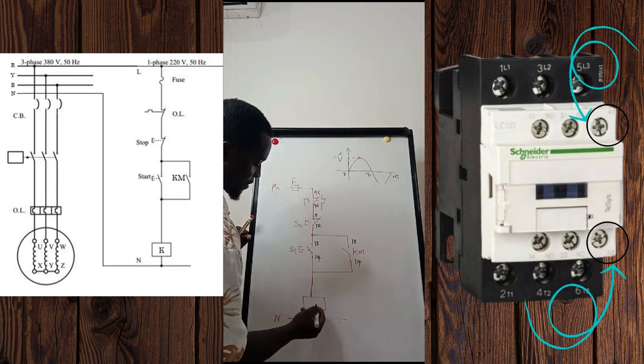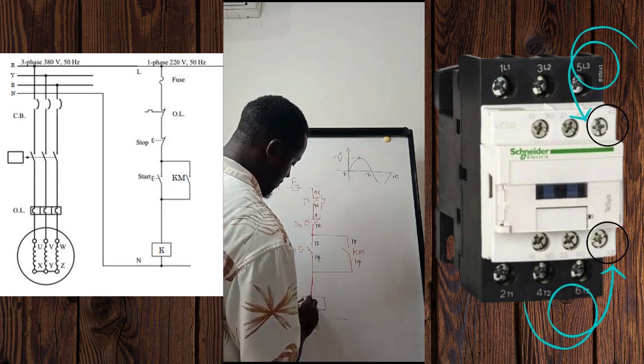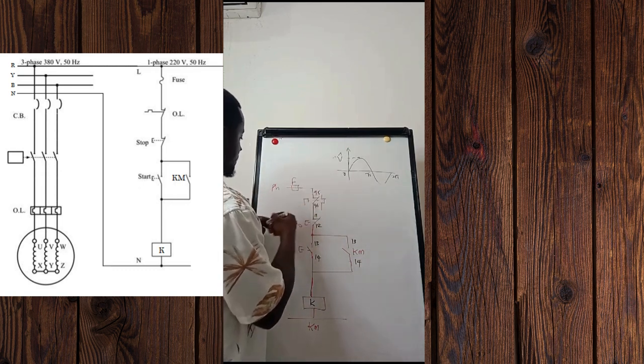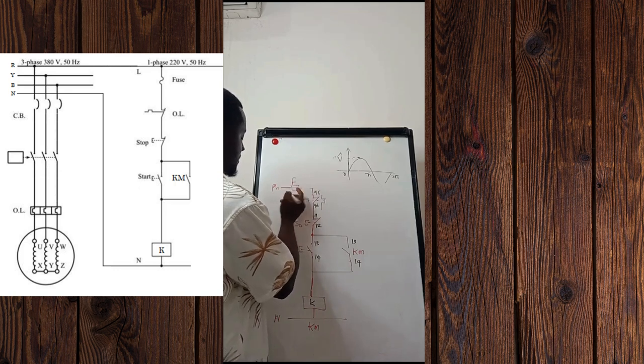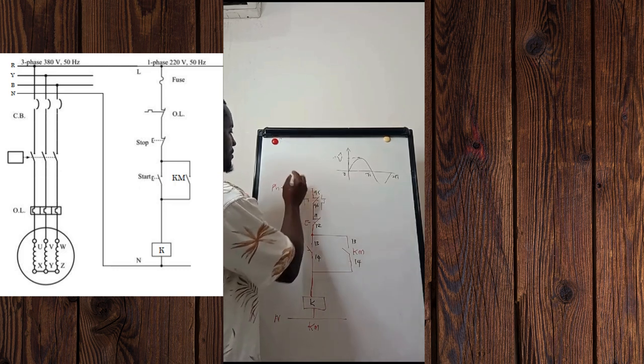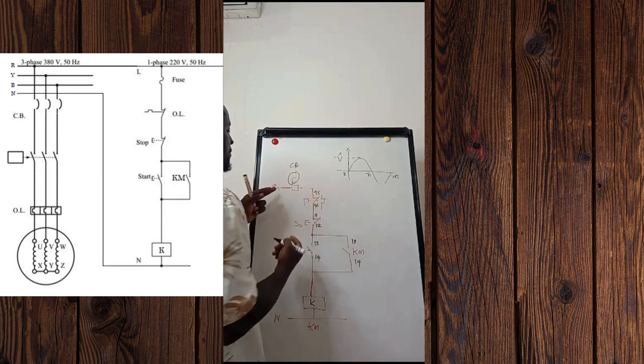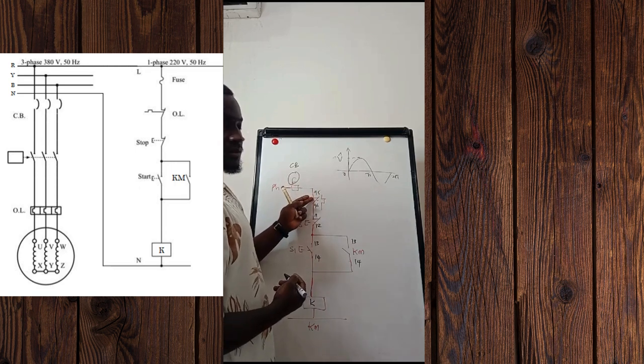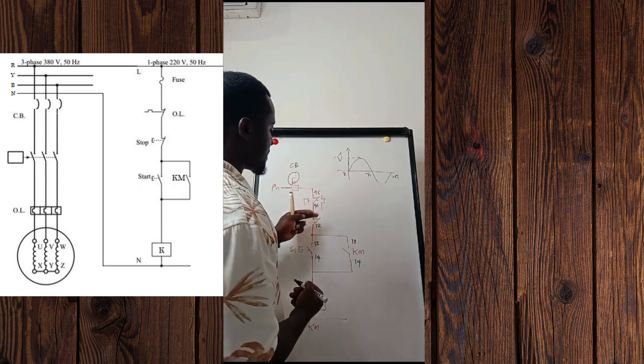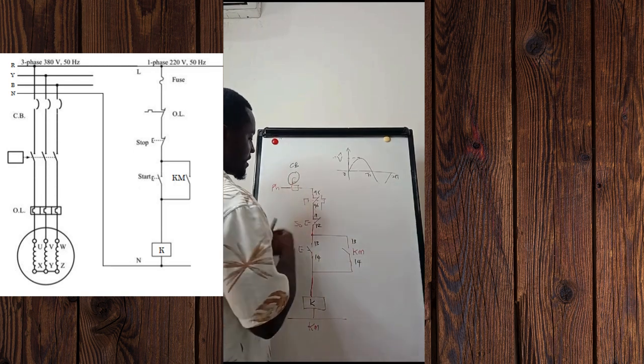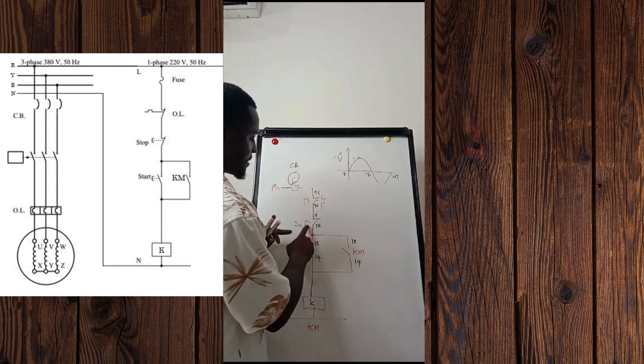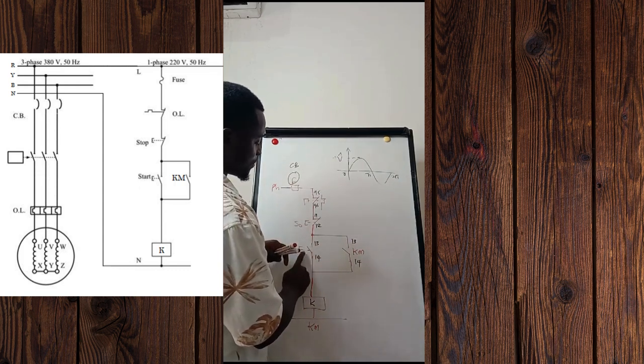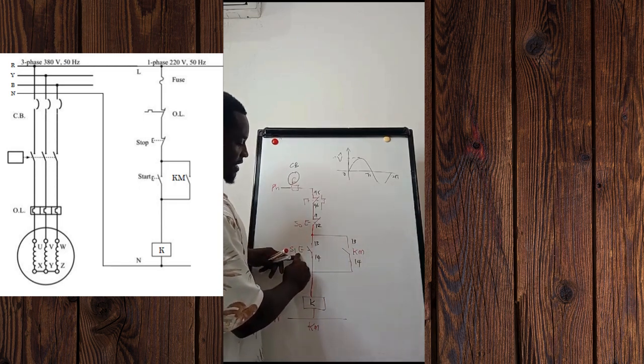Here we have our coil, which we'll call K. Now what happens is when we fit the fuse or the circuit breaker with a single phase supply, current hits first on the normally closed contact of the thermal relay, which is 95-96. Current flows since it's a closed contact, moves and gets to the stop push button S0, and from S0 it moves and gets to the upstream of push button S1.